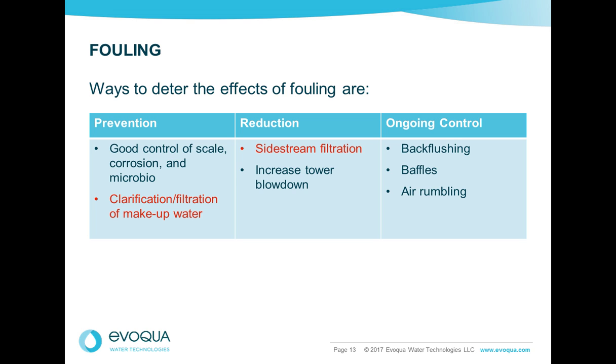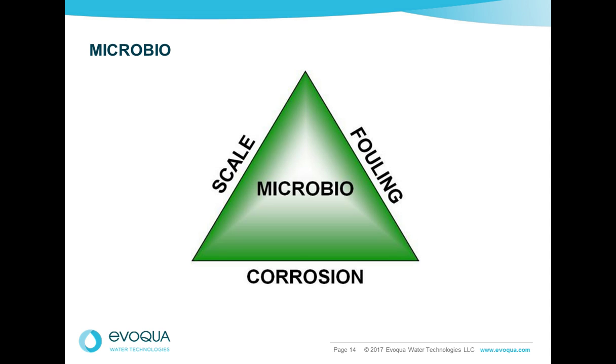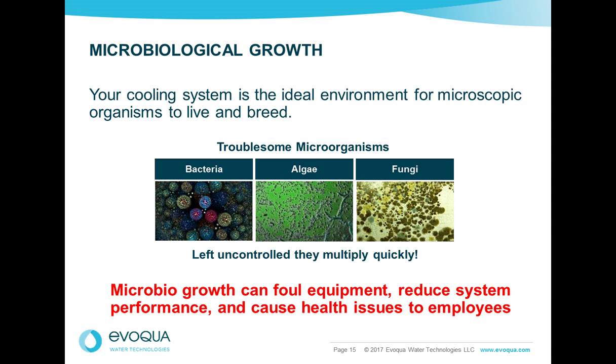Ongoing control involves backflushing, baffles, and air bumping. These are kind of band-aids to fix a dirty system. The easiest way to keep the system clean is to keep the system clean. Use a sidestream filter to continuously remove dirt. Again, we're going back to the triangle: scale, fouling, and corrosion, all aggravated by microbio.